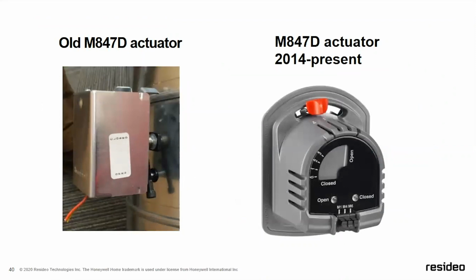Here you can see our old, this is more like a zone motor on the left. The big long screw is what the indicator was for open or closed. You can see on the new actuator, which is 2014 to present, you can actually see whether the actuator is in the open position or the closed position. You can also notice the little red dot on the top. That's your bleed rate, and we'll go over that a little bit later.